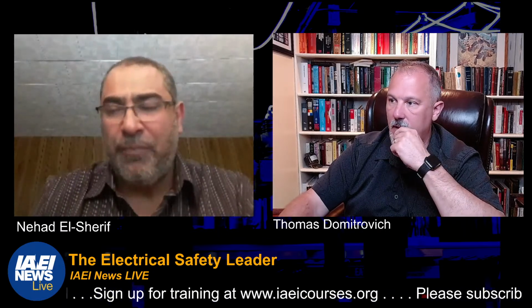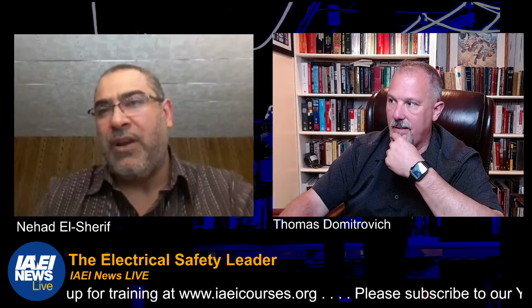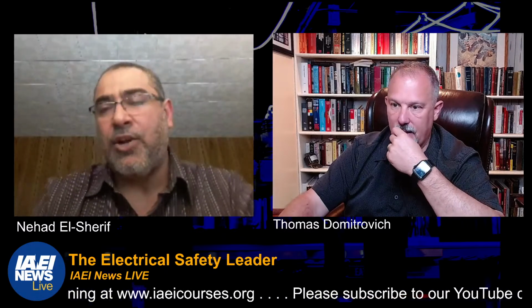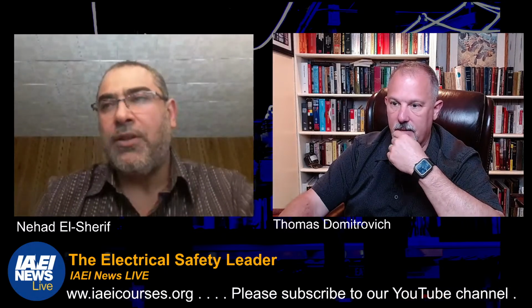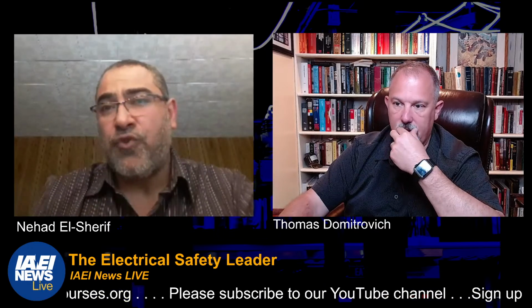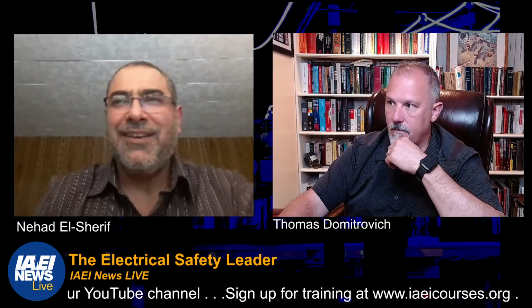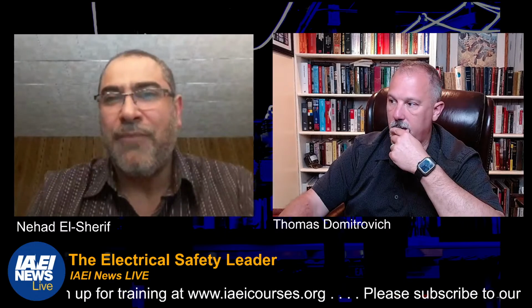Class B back in the day had a 20 milliamp trip level. So I think the 20 milliamp trip level was kind of inherited from Class B GFCIs, which, like I said, are obsolete, but they used to be installed to protect light fixtures for swimming pools. Now it's 2022, almost 2023, and we're going back to protecting swimming pools using Class C, D, and E. After all those years, we're going back to something that was done before. I find it interesting. Yep.